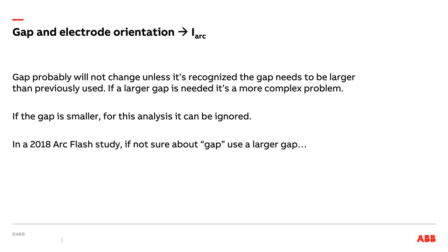So other factors such as the gap between conductors probably is not going to change when you do a study, again, unless people are trying to be very, very exact and they have some exact measurements. Most people will use the so-called recommended or suggested values, typical values in the tables within the guide. And that's the 13, 25, 32, and 40 millimeter numbers that we're familiar with. If the gap happens to be smaller, it actually doesn't matter because it will give you a higher arcing current and less energy, both of which turn out to be conservative variations.